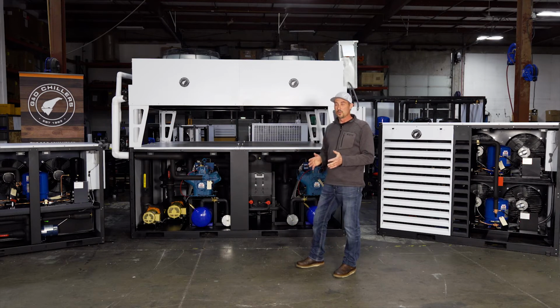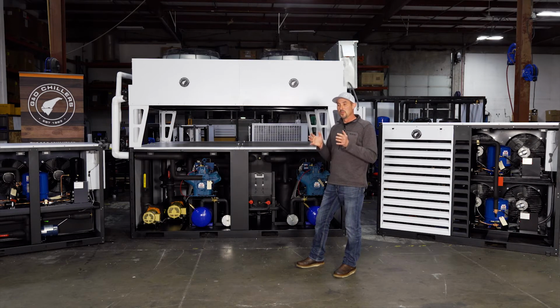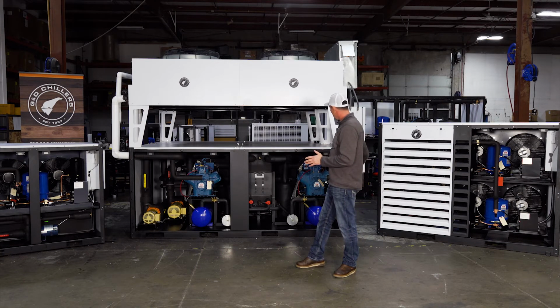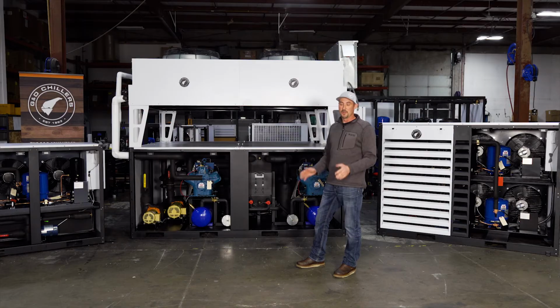The scroll compressor we build chillers with as well, but those are designed more for air conditioning and higher temp applications. They're a great compressor, but when it comes to chiller applications, process cooling in a brewery where we're running much lower temperatures, the reciprocating compressor is the most efficient and most robust style of compressor. So we use reciprocating compressors just for that reason.